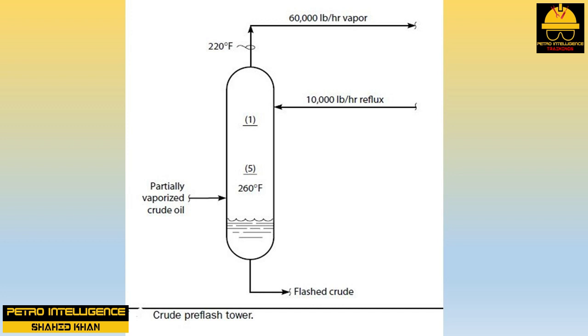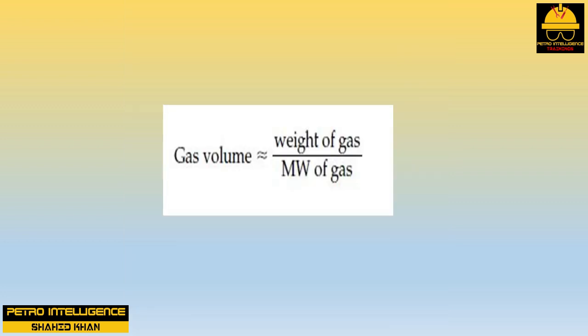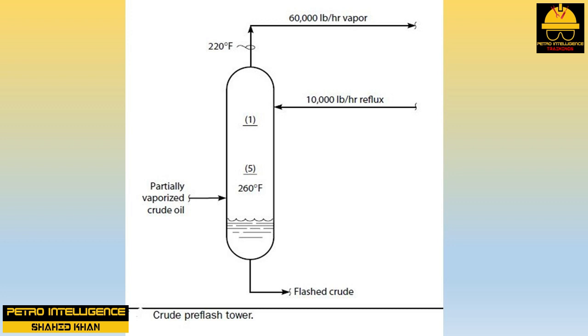A reduction in tower top temperature of 20°F would increase the weight flow of vapor by roughly 10%, but the composition of the vapor would also change — the molecular weight of the vapor would drop by approximately 8%. The lower the molecular weight (MW) of a gas, the greater the volume that a given weight of the gas occupies; gas volume ≈ weight of gas ÷ molecular weight of gas. If the weight of gas goes up by 10% and the molecular weight goes down by 8%, the volume of gas goes up by 18%. The temperature reduction of 20°F shrinks the gas by about 3%, so the net effect of raising the reflux rate is to increase the gas volume through the top tray by 15% (18% − 3%). This results in a substantial increase in top tray pressure drop, which can — and often does — cause the top tray to flood, even though the external heat input and feed rate to the tower have never changed.